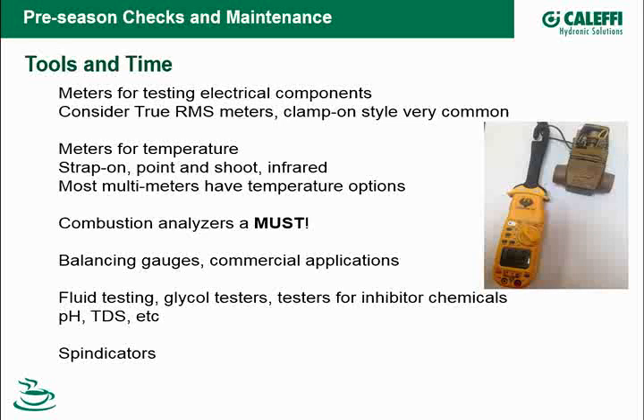Combustion analyzers, this is a must, especially with the high-efficiency equipment that we're putting in today. In fact, most of the boilers that you have, you'll see right in the installation manuals on these ModCon boilers that they want you to set it up with a combustion analyzer to make sure that from day one it's adjusted to the conditions on your job site, to the fuel that's on your job site, and to the conditions on the actual installation.